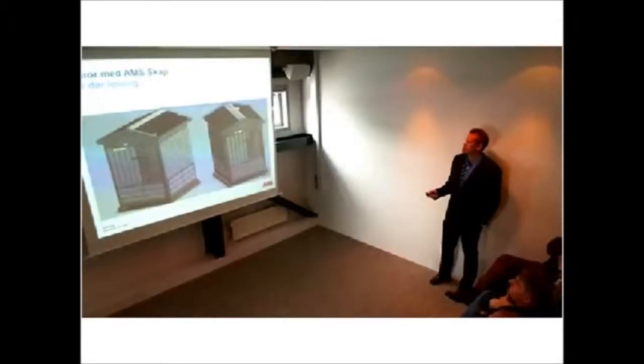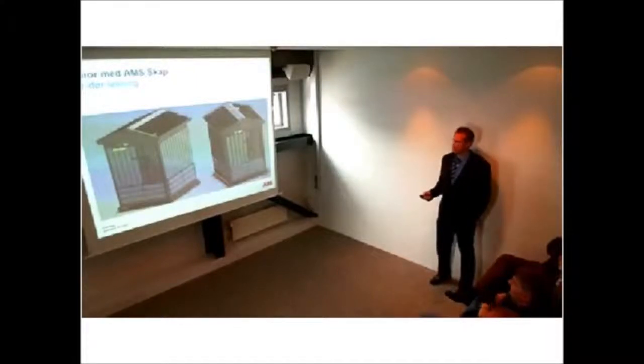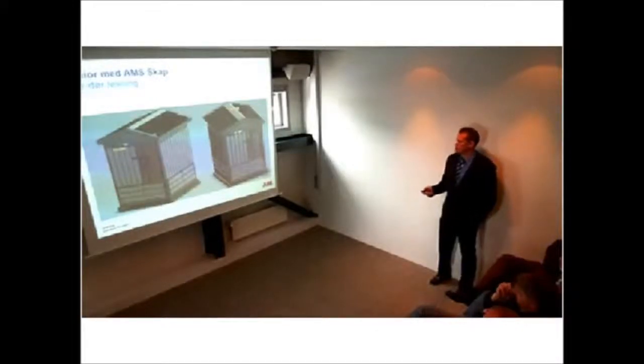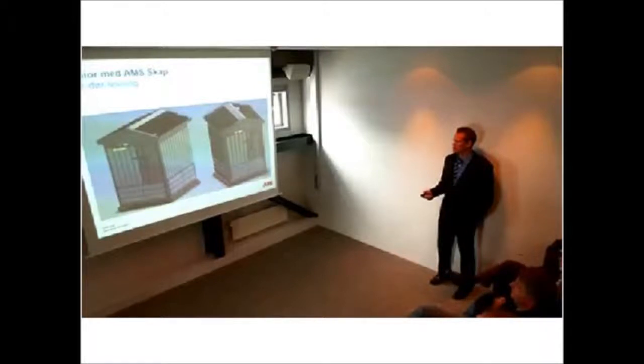Okay, we also have what the customer in Norway wanted, this AMS solution, or AMM. They wanted a door so that people who don't have this certificate can go in and read out the metering for the low voltage, and also for the customer these low voltage connections are attached to. So on this junior substation, we have this door-in-door solution. This is the low voltage cabinet, and then you have one cabinet for this AMM solution.